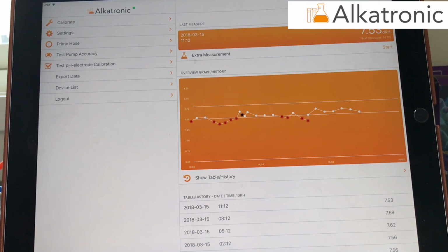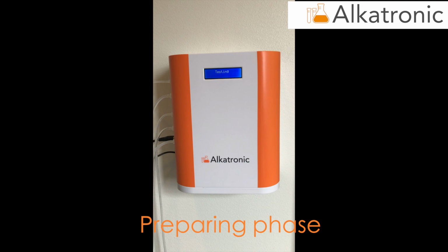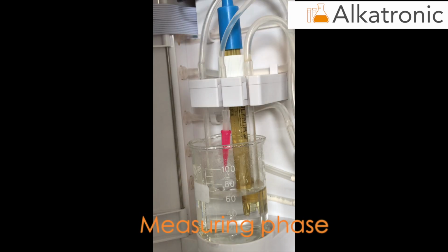I'm pressing start, and you can hear the machine is now starting with the high precision stepper motors to take new water to measure. Here is now the first phase. The machine is now rinsing, and also after that refilling the water to be tested from the aquarium. You see the magnetic stirrer for perfect blending of the reagent and the aquarium water. And you can see the pipette now is distributing the perfect amount of reagent, and the pH electrode will measure the descending pH of the water. This process is proceeding until the machine is ready.